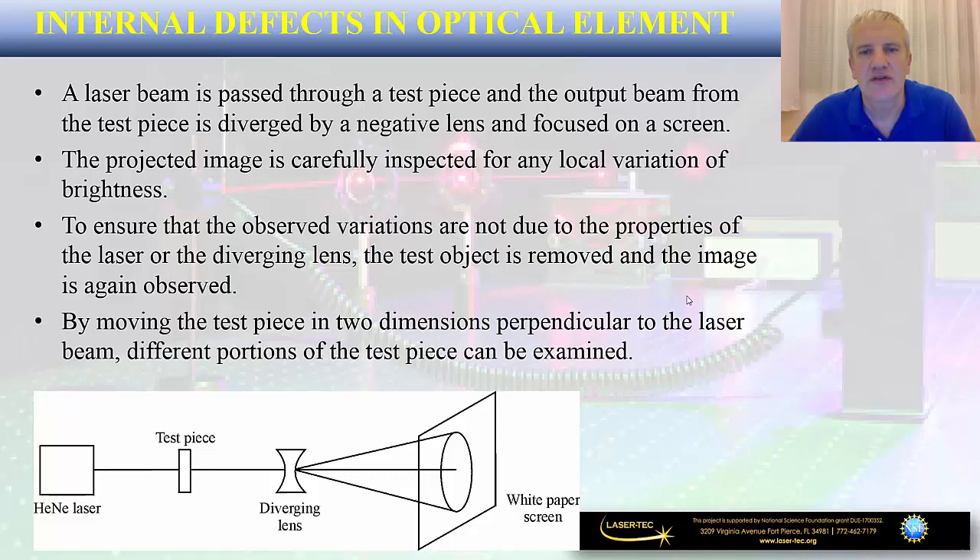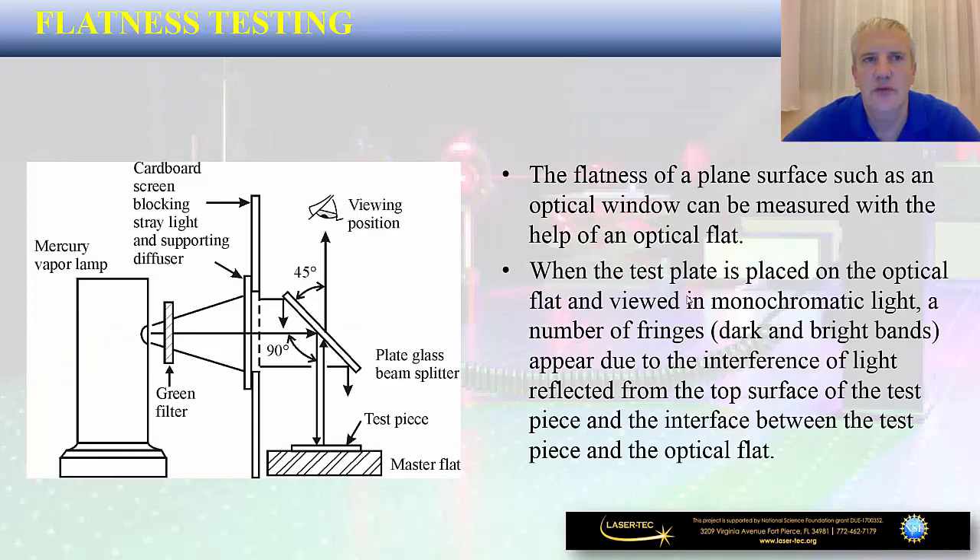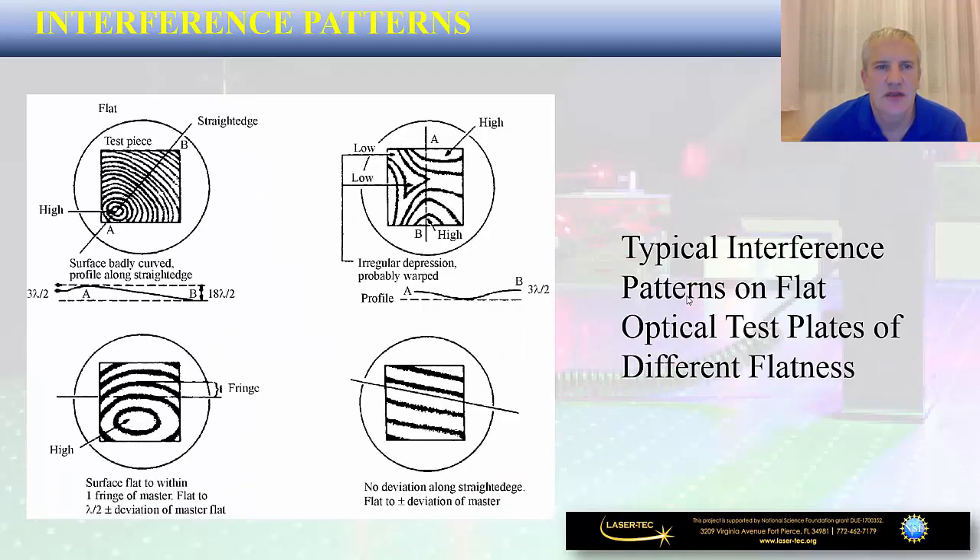Another important test to be performed on optical components is so-called flatness testing. Flatness testing is performed on a plane surface of a specific type of component such as an optical window, and it can be measured with the help of a so-called optical flat. The optical component to be inspected is placed on this optical flat and then viewed under monochromatic light. You are looking for fringes — dark and bright bands that appear due to the interference of light reflected from the top surface of the test piece. This type of testing is very often performed in photonics labs when you are interested in the quality of flatness of a specific type of optical window.